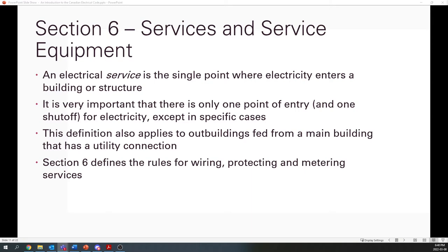So again, I emphasize it's the single point where electricity enters the building. So it is very important that there's only one point of entry, and that follows that there's one shutoff for the electricity entering your building, except in specific cases where you might have a very, very large building, for example, an airport, that needs multiple feeds of electricity, or where one feed would just not be economical, to have one massive feed for the whole building.